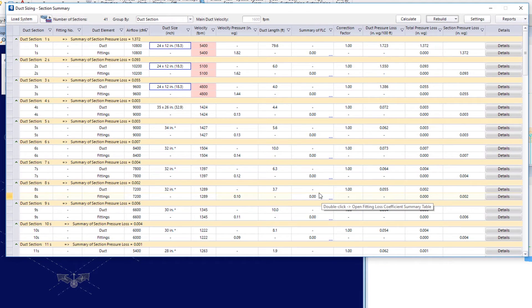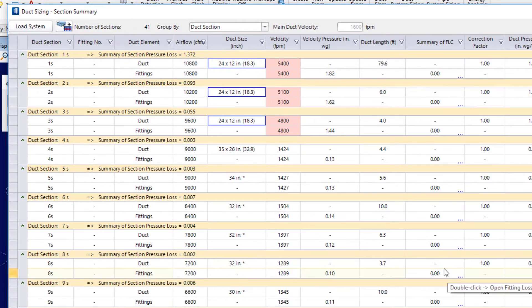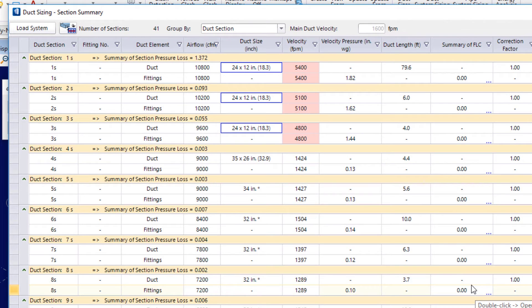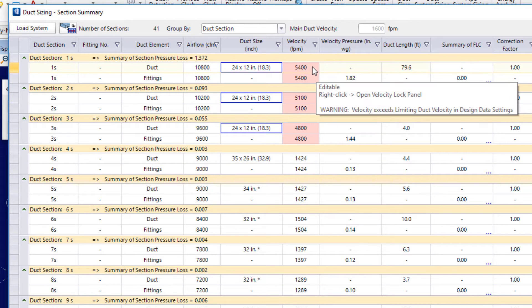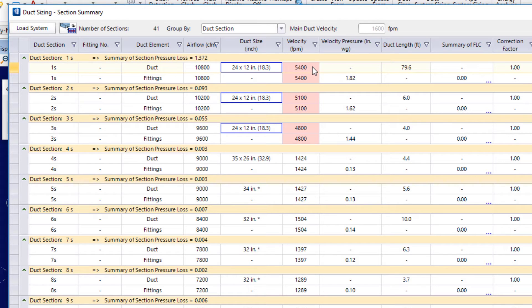Now, I see that my velocity for those sections is showing me the red background for that field. So, that's a heads up. If I hover over this field, I see that it's editable. I can right click to open up the lock panel for the velocity. But I also see there's a warning. Velocity exceeds limiting duct velocity in design data settings.